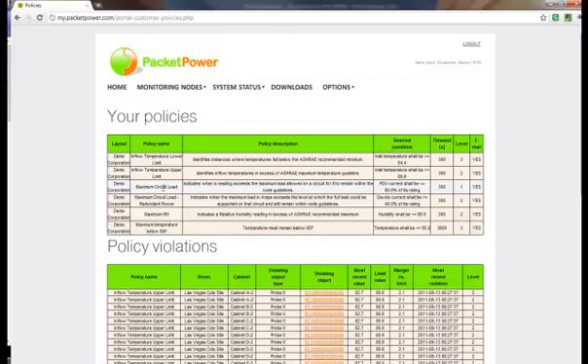The third deals with maximum circuit load for cabinets that don't have redundant power and will notify you if the load exceeds 80% of the circuit's rating. The fourth is for redundant power cabinets and will notify you if the current exceeds 40% of the circuit's maximum rating.